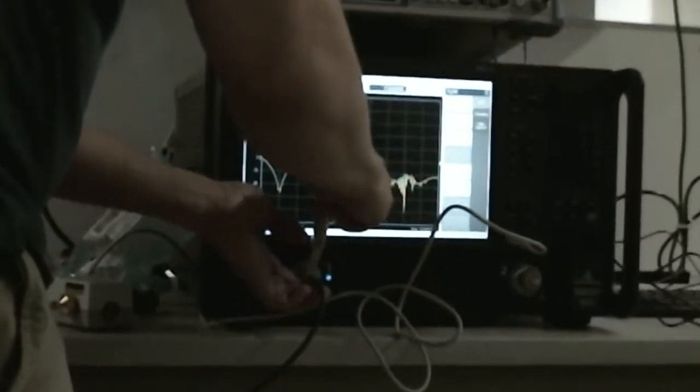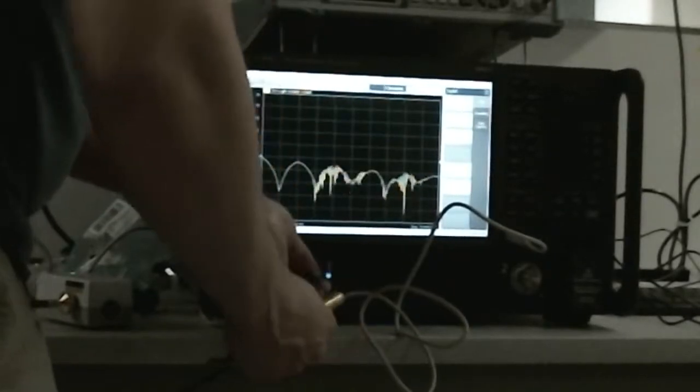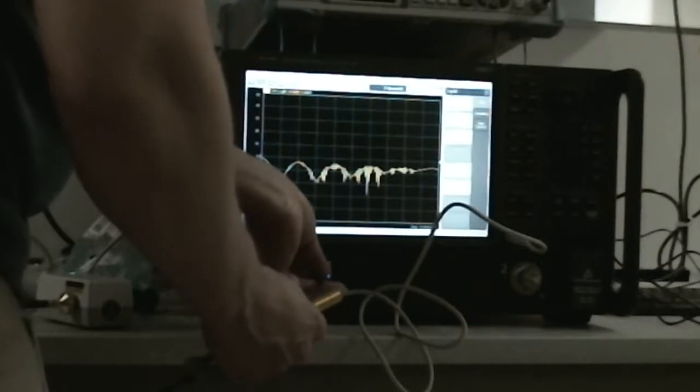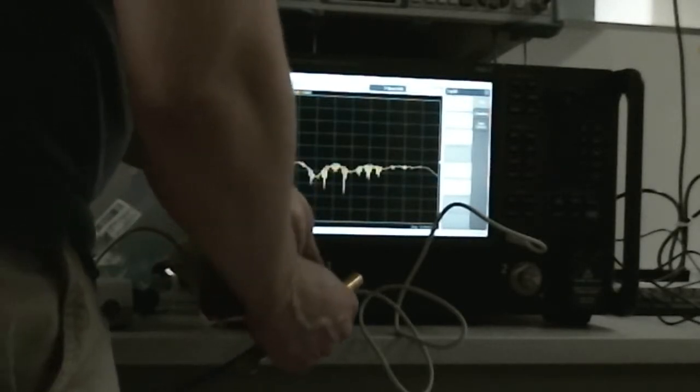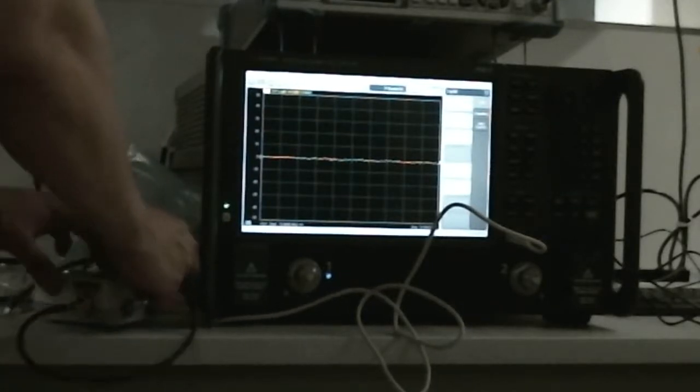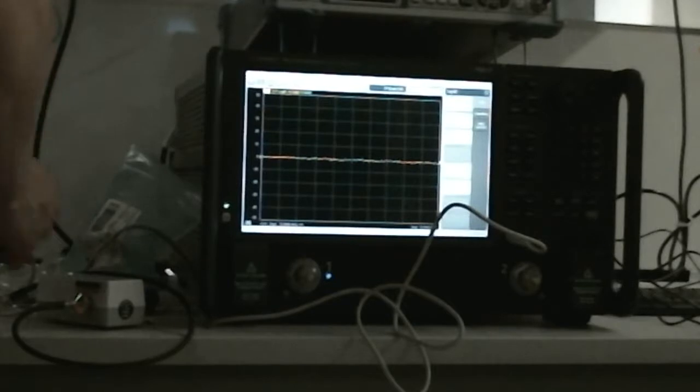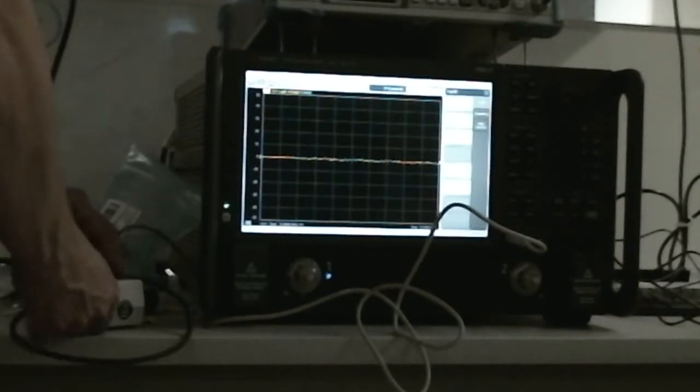So what I'm going to do is I'm going to actually do my calibration. I'm actually going to do the calibration right at the instrument ports. So this means that it's going to be fully calibrated there. You know, because it's within 13.5.